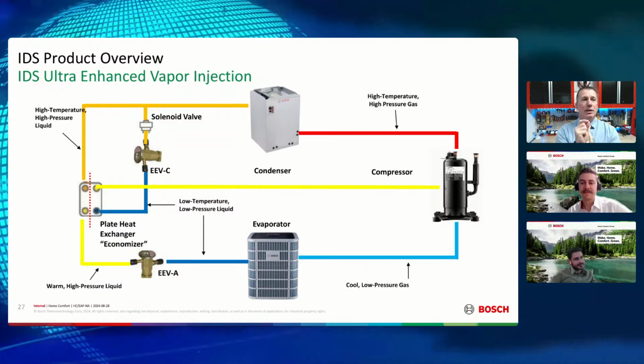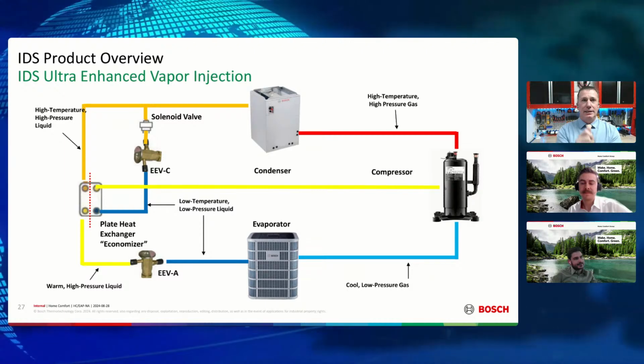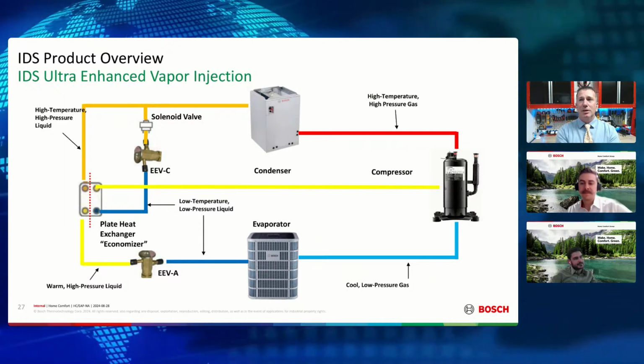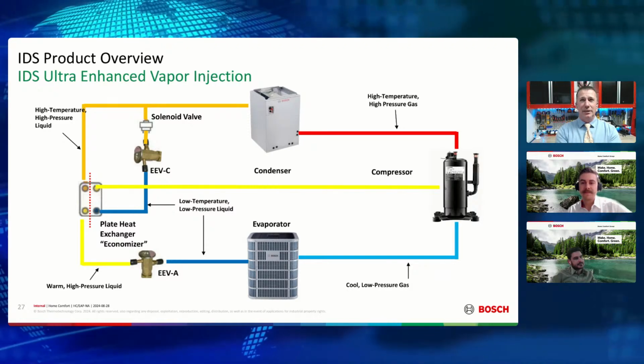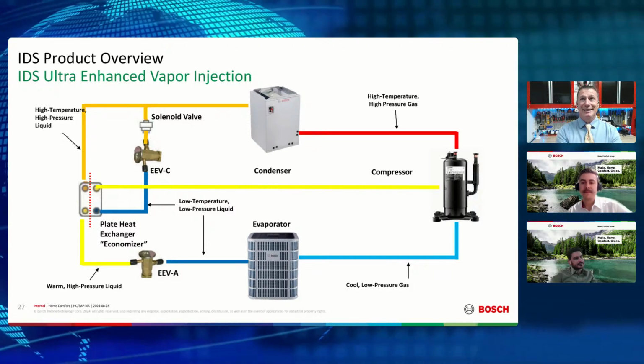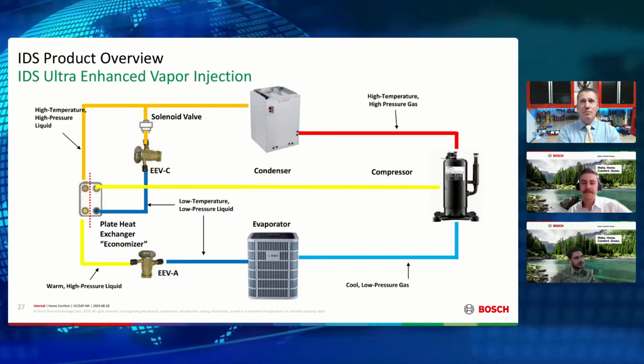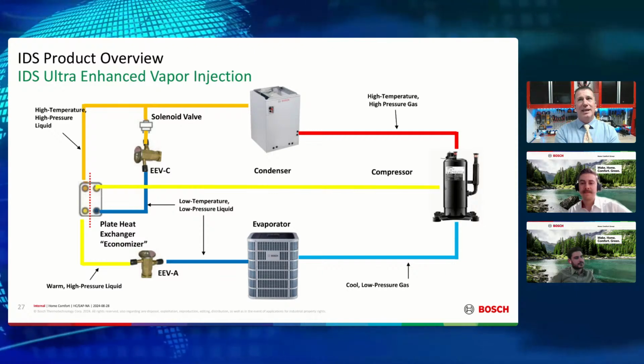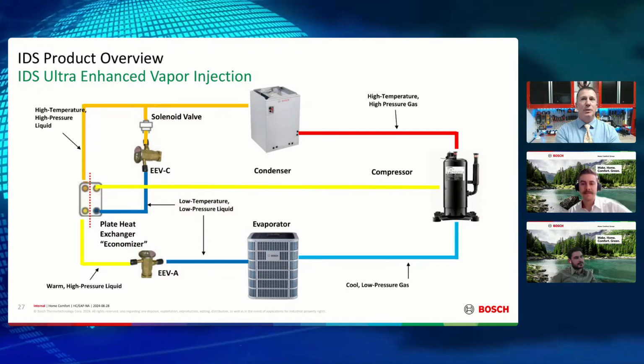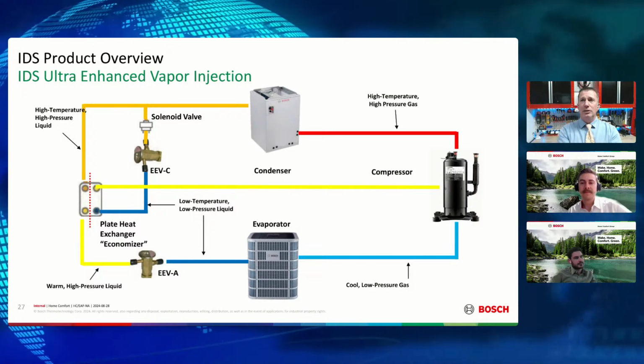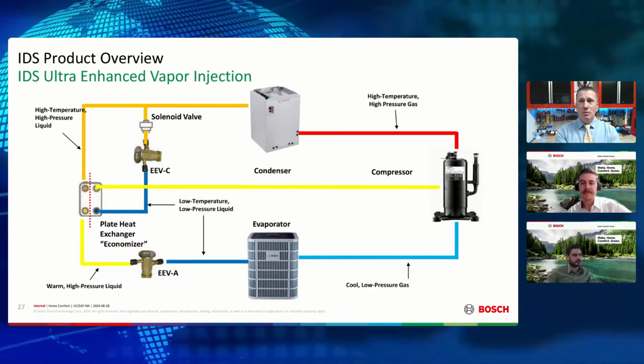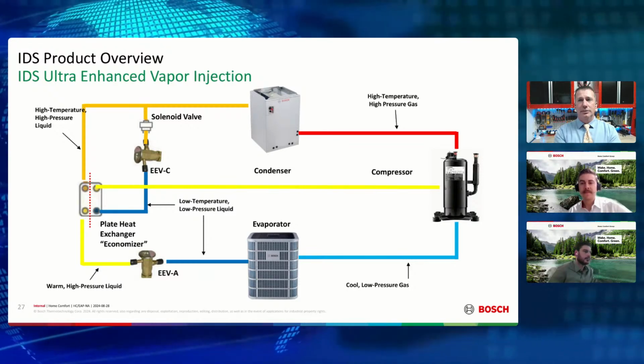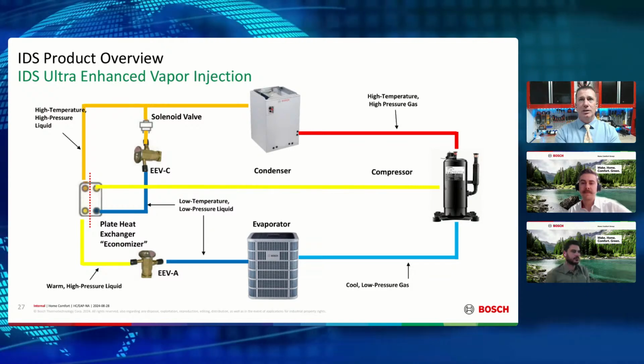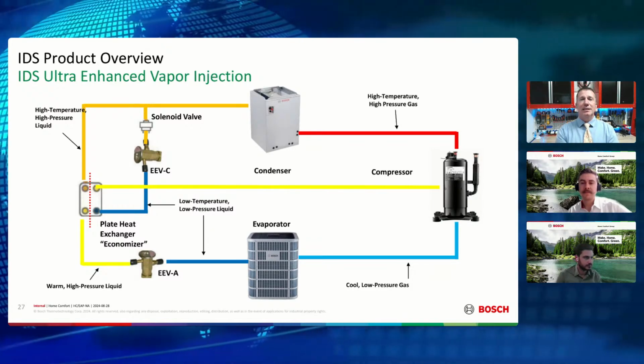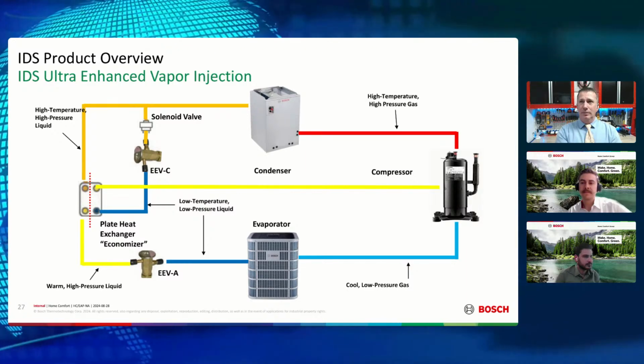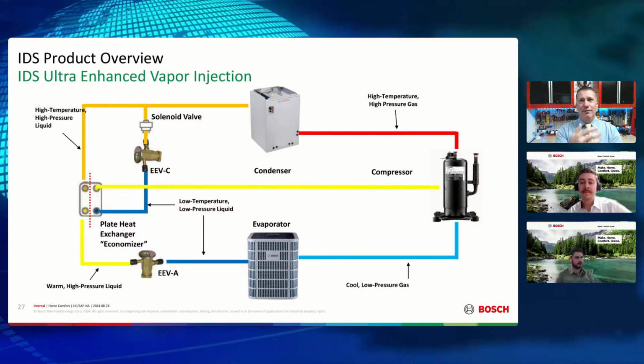Exactly. For those struggling with understanding dehumidification capability with an inverter, I believe it's just because you haven't given us the chance to show you the benefit of the inverter for dehumidification, especially when we have dry mode. In dry mode, we're probably going to adjust that evaporator target temperature down a little bit and reduce that fan speed, just exactly what you were saying, Mohamad. We're going to maintain based on humidity control versus traditional temperature control and changing fan speeds to adjust humidity. So the capability of these systems in southern climates is more important than we have traditionally thought.